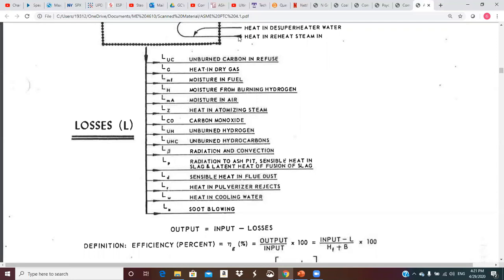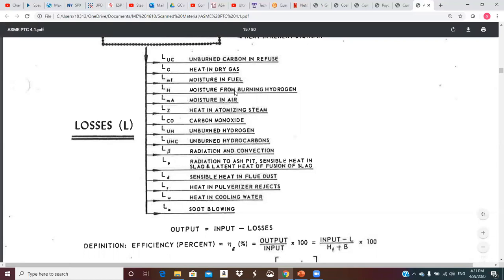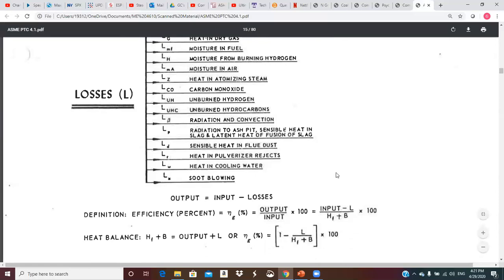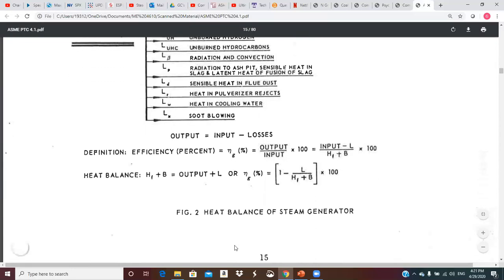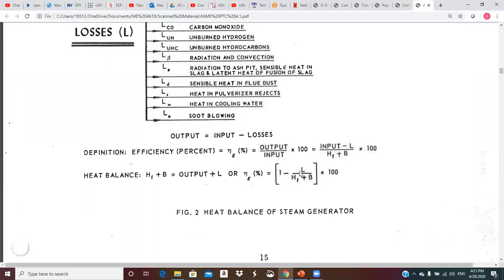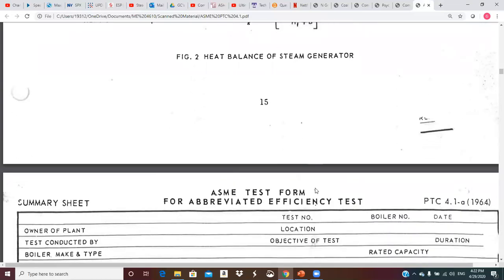So potentially 15 potential losses. So output is equal to input minus losses. You can do a little bit of algebra here. And so you wind up with an equation, one minus the losses divided by the chemical energy plus the sum of the credits, times a hundred is your boiler efficiency, or you can just do it output divided by input or input minus losses divided by input. So you've got two different equations there that can be used.